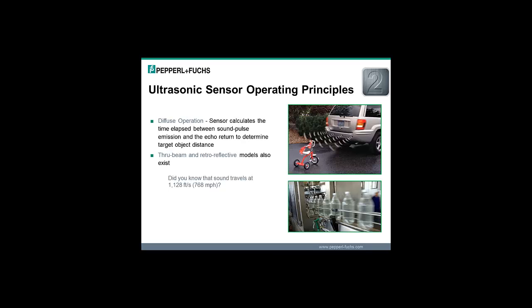The other modes that are more application solvers are Thru-Beam. You can see with the bottles coming down that line, the clear bottles on the bottom right-hand corner, typically that's going to be a Thru-Beam application. And there's also a retroreflective mode. Just like a photo eye looks at a reflector, the ultrasonic can look at a target object or a flat panel and use that as a reflector, and as an object comes past, it breaks the beam, and you have an ultrasonic retroreflective sensor. So those are the three operating principles used by ultrasonic sensors.